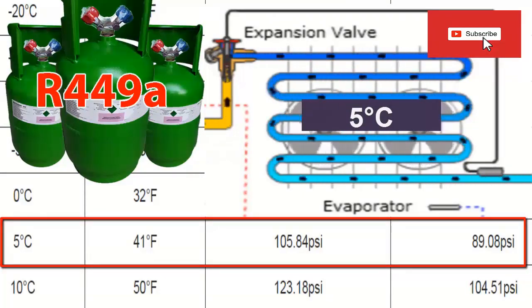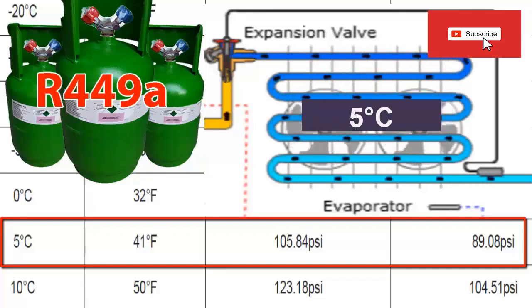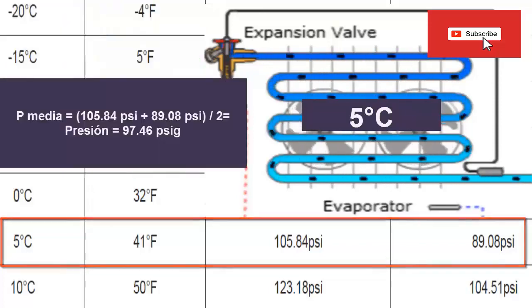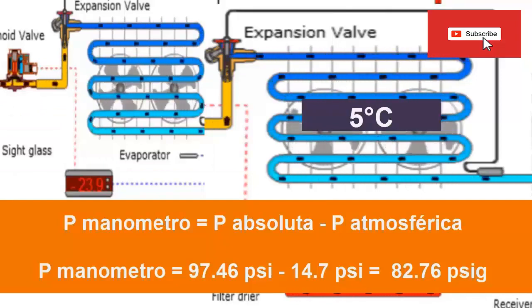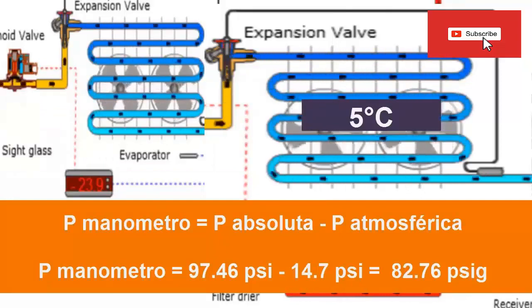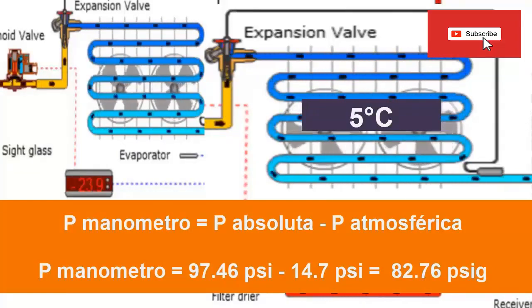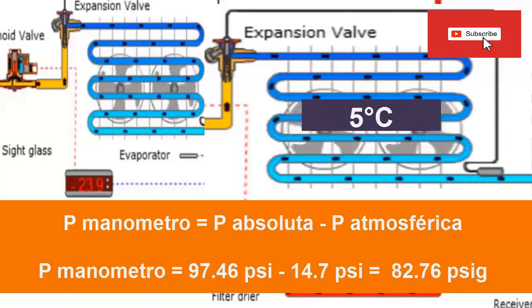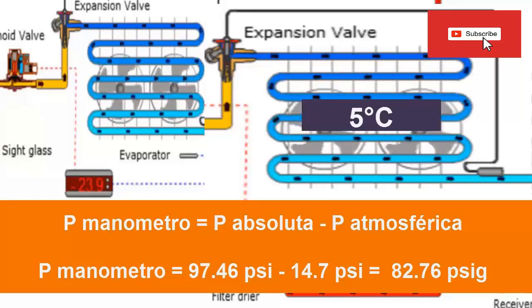For example, by taking the average between these values, you have an absolute pressure value of 97.46 psi. By subtracting the atmospheric pressure, you have an average working pressure of approximately 82.76 psi G. Although it is not exact, we can say that with an evaporator pressure of 82.76 psi G, we would be very close to reaching the temperature of 5 degrees in the middle of the evaporator.